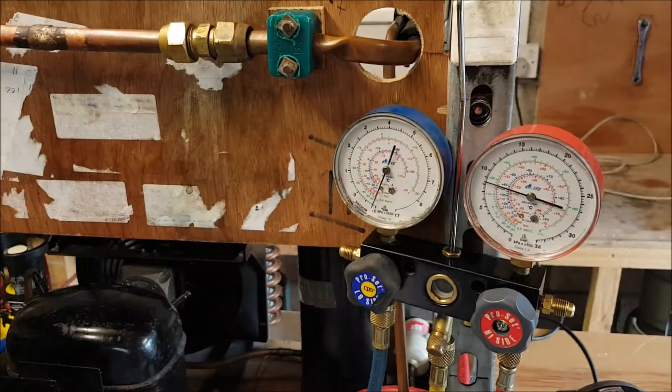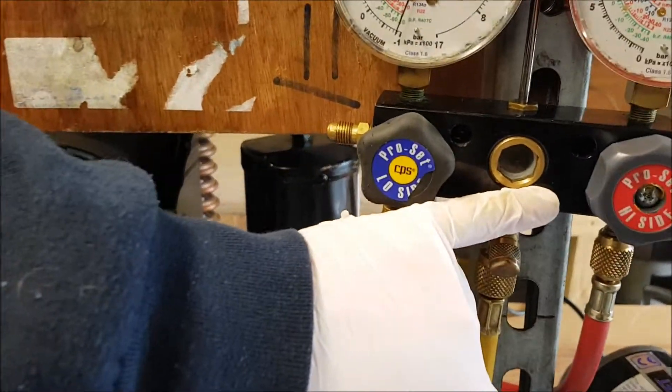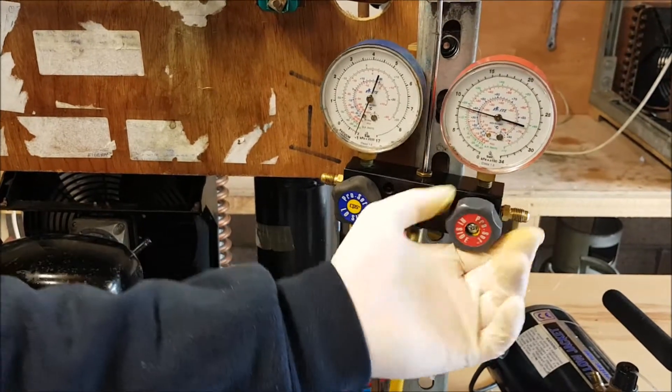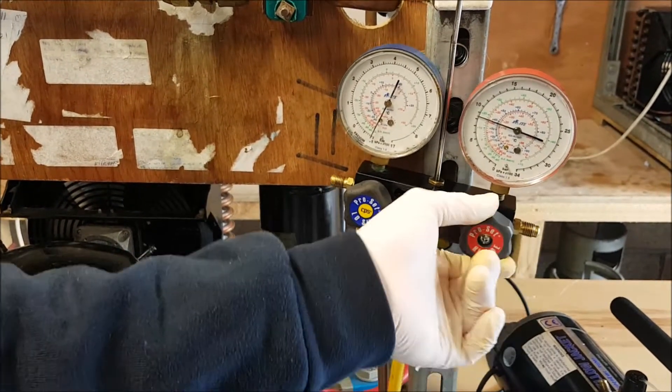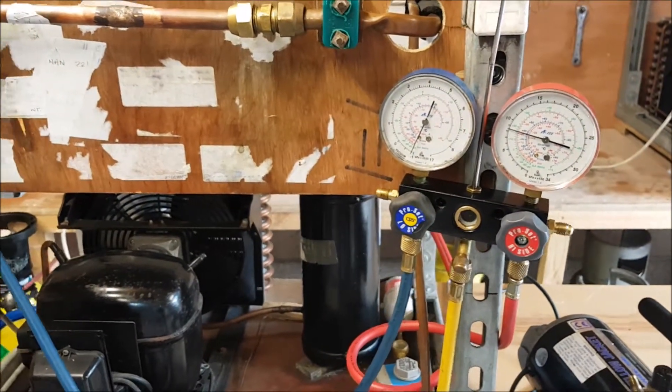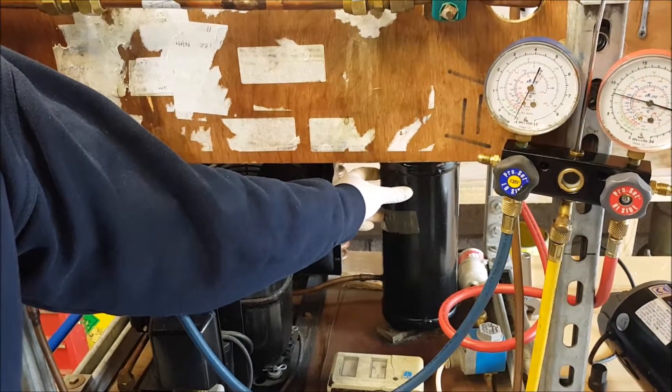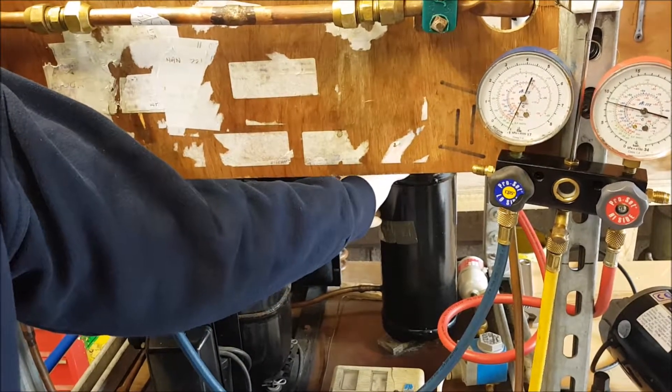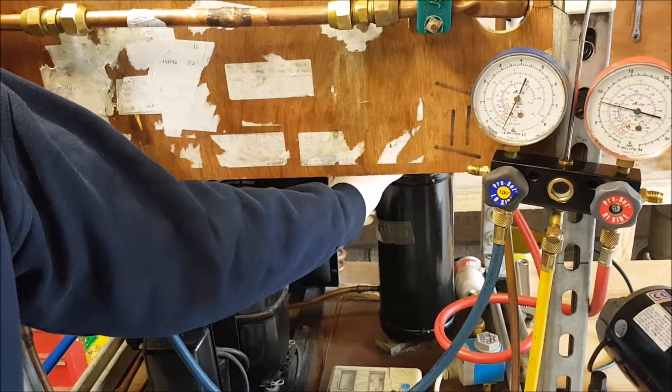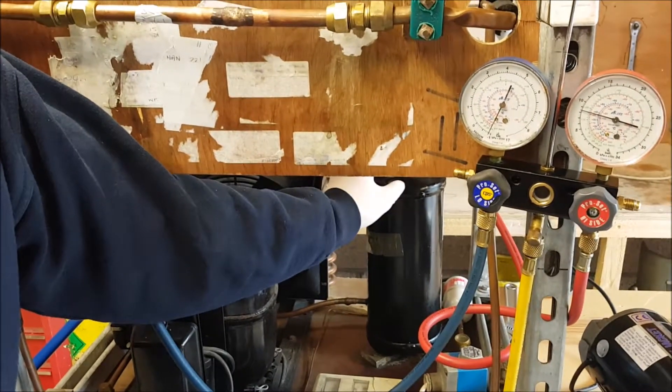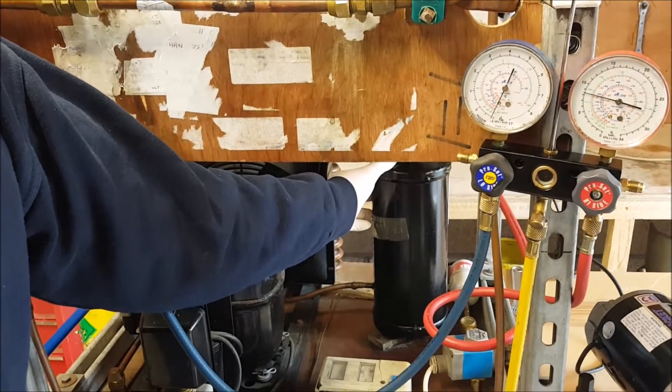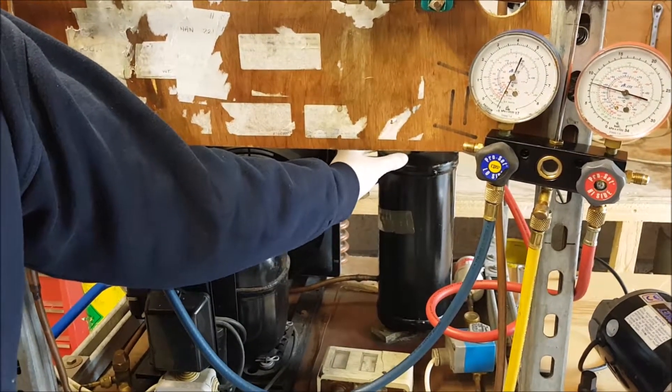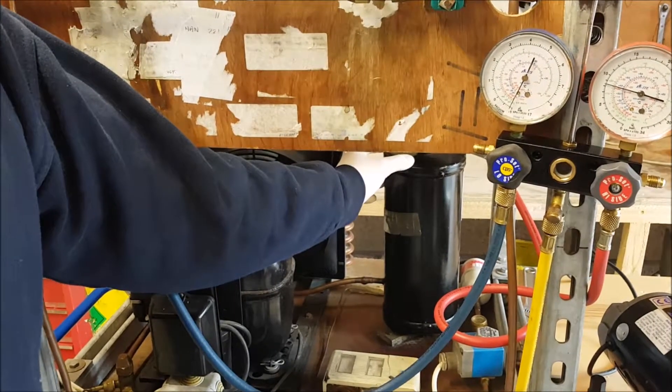The pressure here is equalized with the pressure in the bottle. You can see in our sight glass on our manifold no more liquid refrigerant is now entering the system. I have to run the system and then decide whether I need to add more refrigerant or whether I have it perfectly charged. Under normal circumstances, the liquid receiver is supposed to be sized to contain the maximum amount of refrigerant that system will hold. These receivers, unfortunately, because of training purposes, have been oversized.